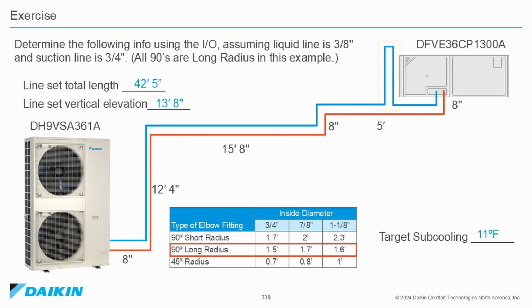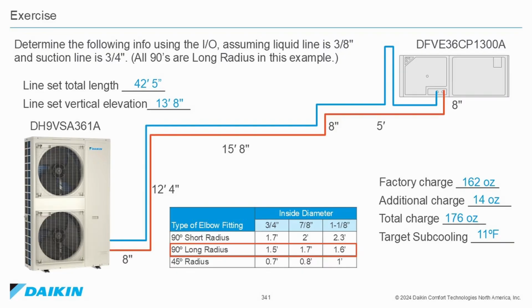Also notice that the suction line has a reverse trap that rises above the top of the indoor coil. We see by the I/O manual and the data tag on the outdoor unit, the factory charge is 162 ounces. By using the I/O manual and calculating the total liquid line length, we see the additional charge is 14 ounces, which gives us a total charge of 176 ounces, with the target subcooling of 11 degrees Fahrenheit.